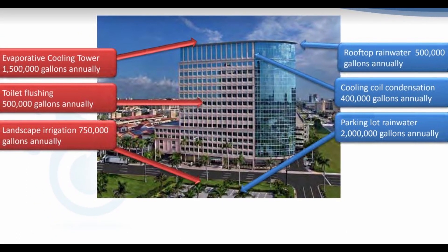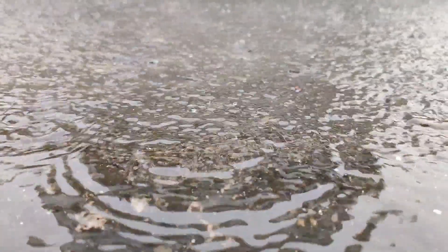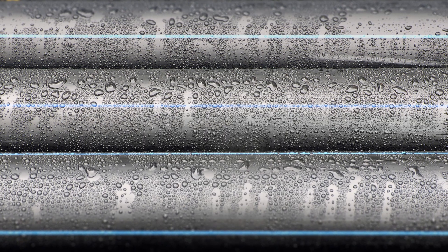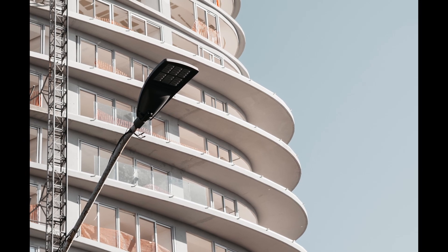This can make a dramatic impact on how much water you can save. Let's look at the top four sources of water that can be reused: rainwater, which can be collected from roofs; stormwater, which is collected at grade; greywater, which is collected from gently used water in sinks and showers; and cooling condensate, which is collected from air conditioning coils. Most buildings have two or more of these sources available.